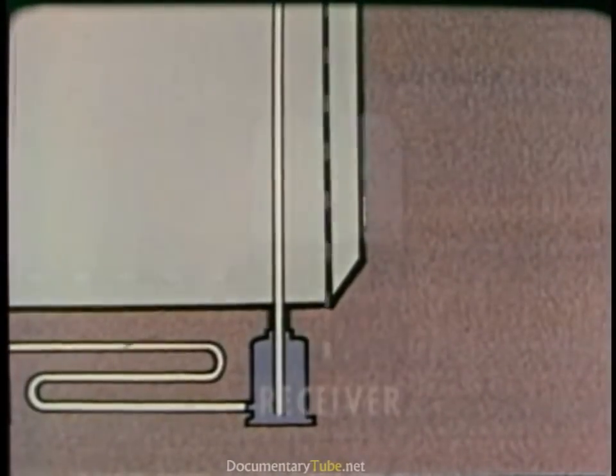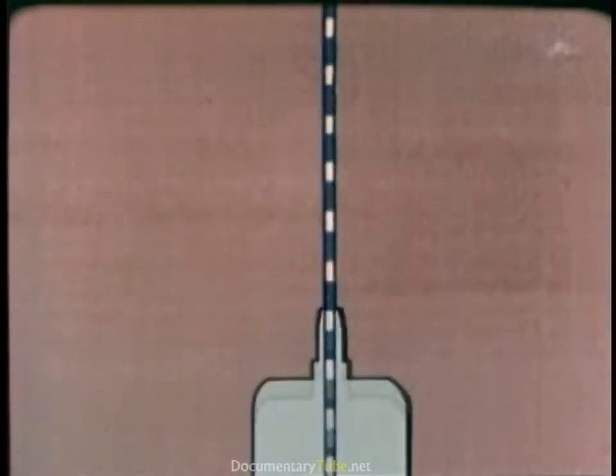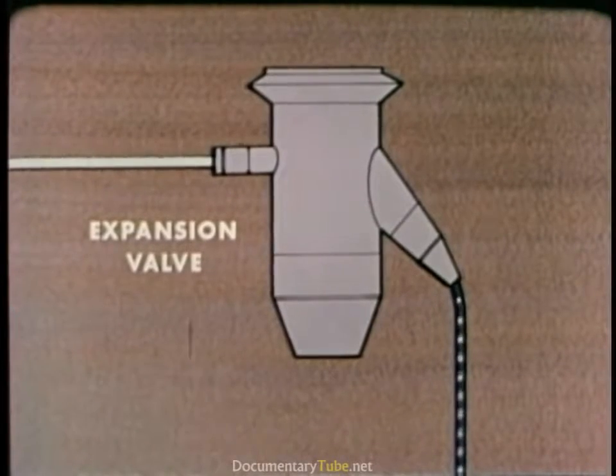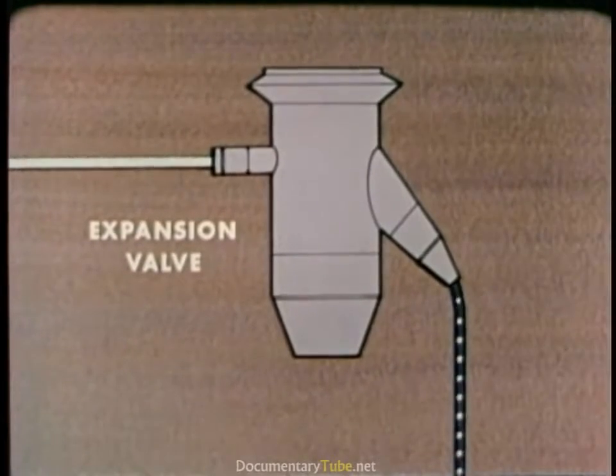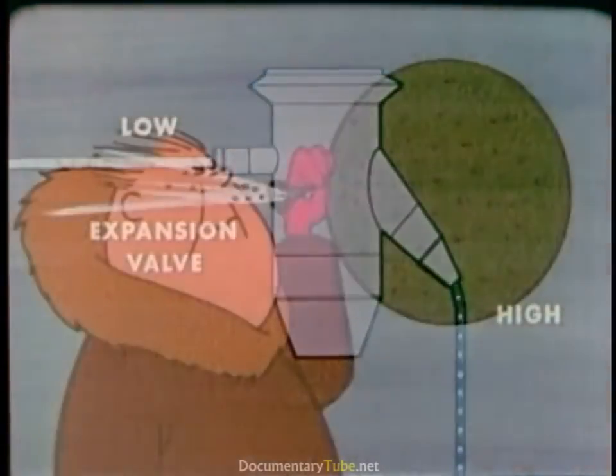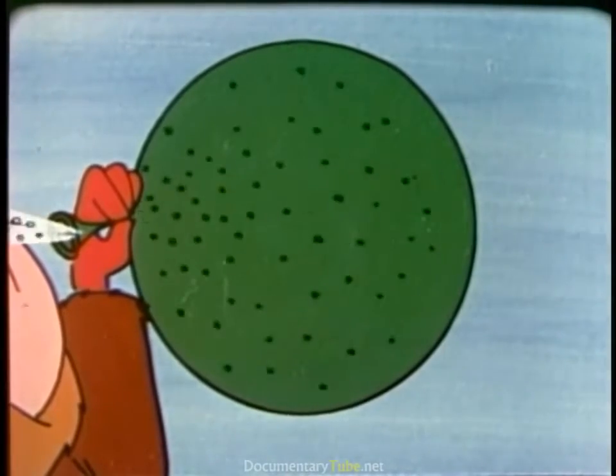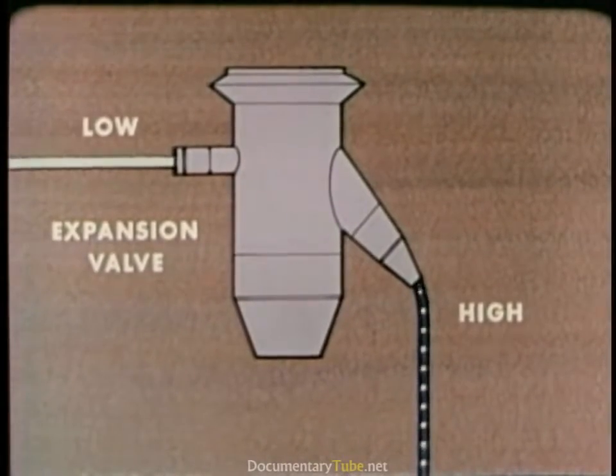Now let's see how a refrigerator works. We'll begin at the receiver where the excess refrigerant is stored. It is in the liquid state and under high pressure. The high pressure forces the refrigerant through the liquid line to the expansion valve. This valve causes a pressure drop. The high pressure liquid becomes a low pressure liquid. This is like letting air slowly out of a balloon. The air in the balloon is still under high pressure, but the air that gets through expands and its pressure drops. In the same way, refrigerant that passes through the expansion valve expands and its pressure drops.